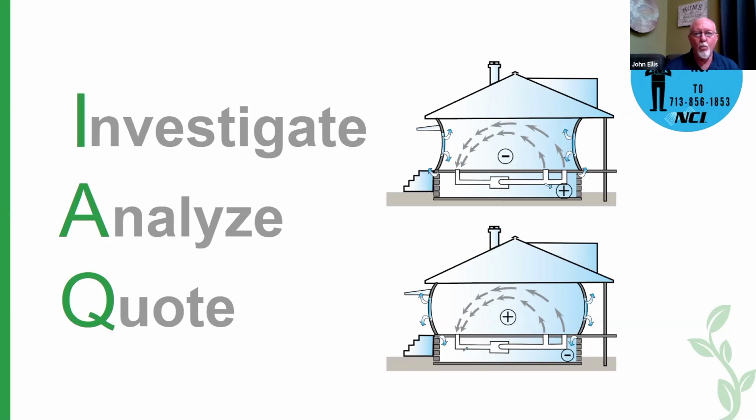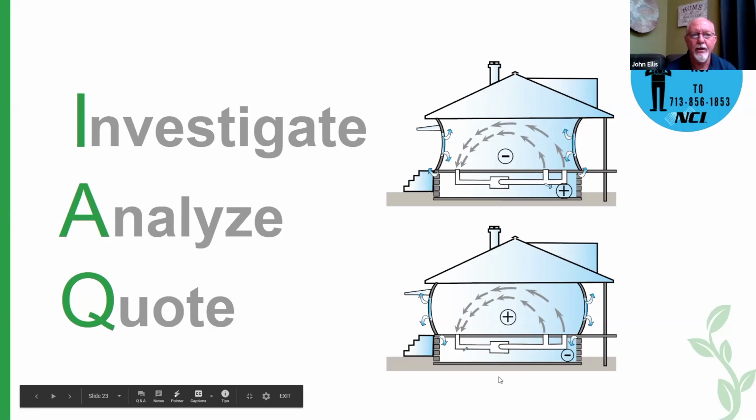On the wet side of the country, we offer ERVs, which temper the air but also remove the humidity before bringing it into the home, which is critical in the wetter climates. Also, a dehumidifier can be used both as an outside air intake, but also internally in the home, just recirculating to mitigate humidity. These are some of the strategies that we use for bringing in a prescribed amount of outside air, fresh air.